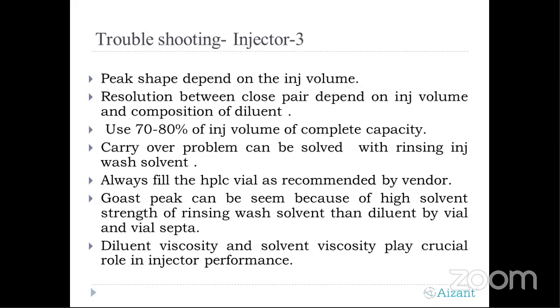Now, the carryover problem means that a previous injection is coming in the next injection. After the peak of the sample you have injected, you find in the next injection that there is also a peak appearing. That is called carryover. With advanced instruments it was taken care of, but the rinsing solvent or wash solvent we use in the advanced system is also a crucial one. When we use a wash solvent with a different polarity with respect to the chromatography we are using, it will end up in a carryover problem.